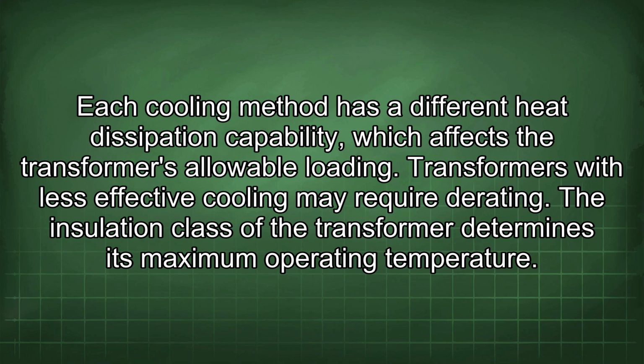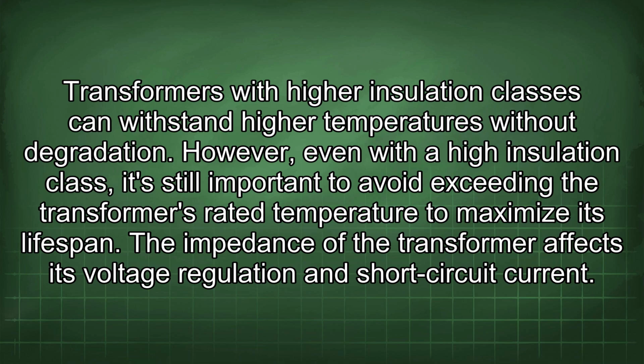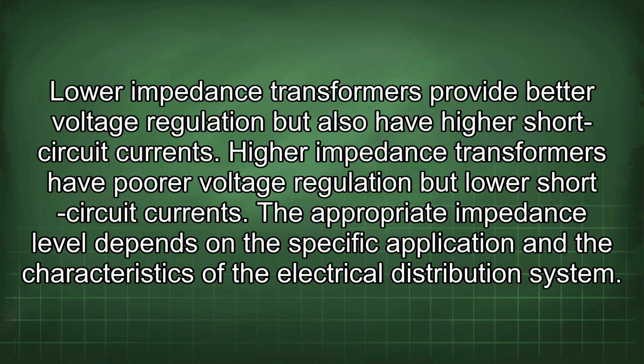The insulation class of the transformer determines its maximum operating temperature. Transformers with higher insulation classes can withstand high temperatures without degradation. However, even with a high insulation class, it's still important to avoid exceeding the transformer's rated temperature to maximize its lifespan. The impedance of the transformer affects its voltage regulation and short-circuit current. Lower impedance transformers provide better voltage regulation but also have higher short-circuit currents. Higher impedance transformers have poorer voltage regulation but lower short-circuit currents. The appropriate impedance level depends on the specific application and the characteristics of the electrical distribution system.